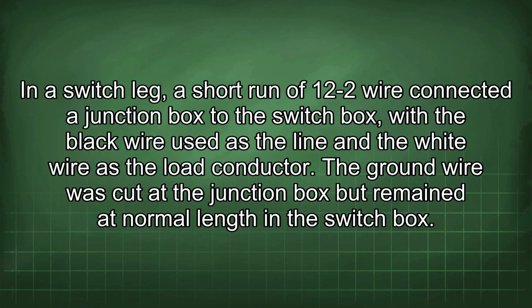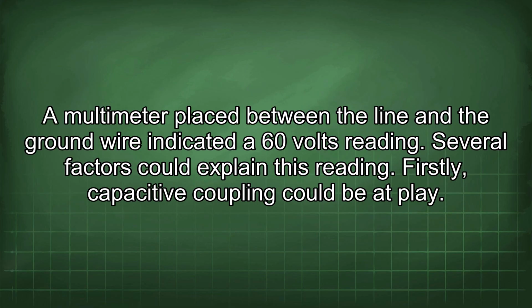In a switch leg, a short run of 12-2 wire connected a junction box to the switch box, with the black wire used as the line and the white wire as the load conductor. The ground wire was cut at the junction box but remained at normal length in the switch box. A multimeter placed between the line and the ground wire indicated a 60 volts reading. Several factors could explain this reading.